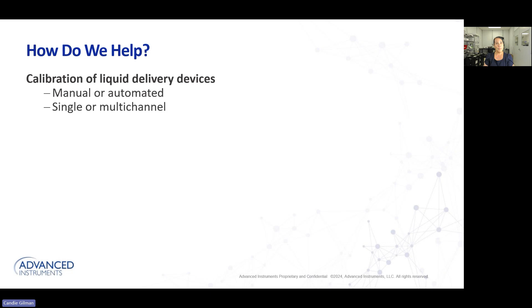And then time and rework really go hand in hand. Again, what's the cost for having to rerun a test? What's the cost for having to scrap product that has to be reworked because maybe there's been too much variability in the pipetting steps along the way? So how do we help, right? Certainly calibration of liquid delivery devices. So those liquid delivery devices might be manual devices, or they might be automated liquid handlers. They might be single channel devices or multi-channel devices.